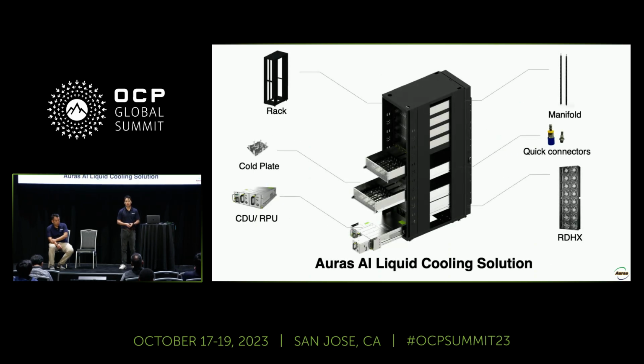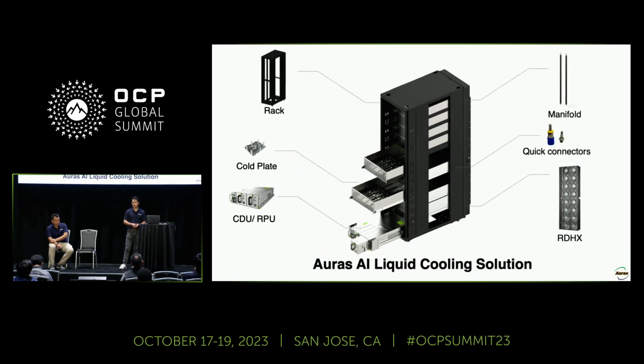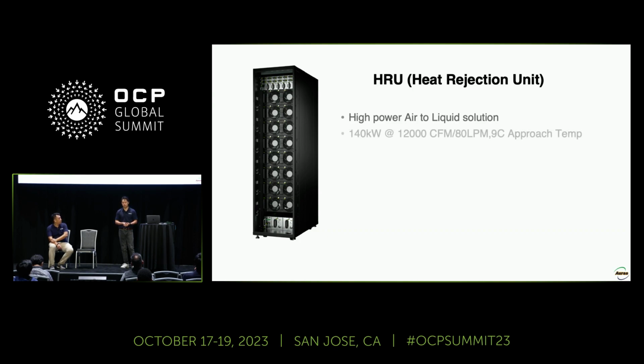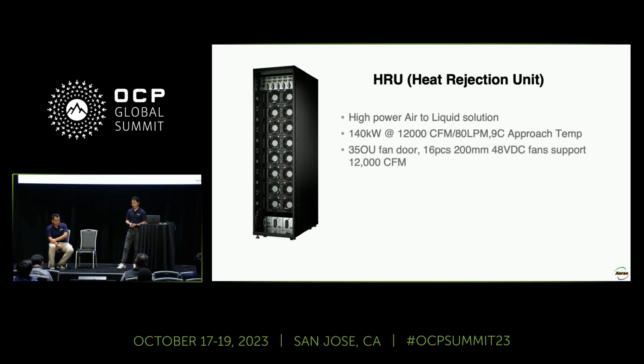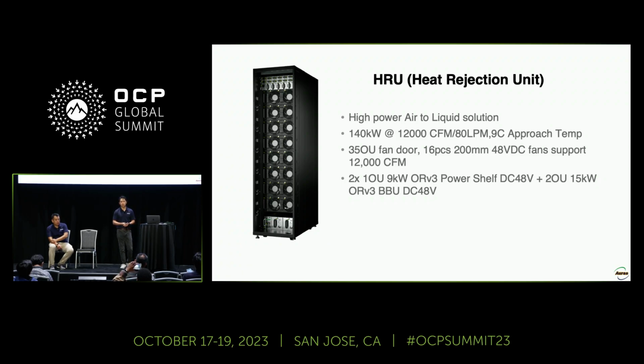So what if we combine all the components together? What kind of solution can you get? It will be our heat rejection unit. It's a high power air to liquid solution. We can support up to 140 kilowatts at 12,000 CFM with the 9 degrees Celsius approach temperature. It comes with the 35U fan door with 16 pieces of fan supporting up to 12,000 CFM. It also comes with 2 sets of the power shelf and 2 sets of BBU.